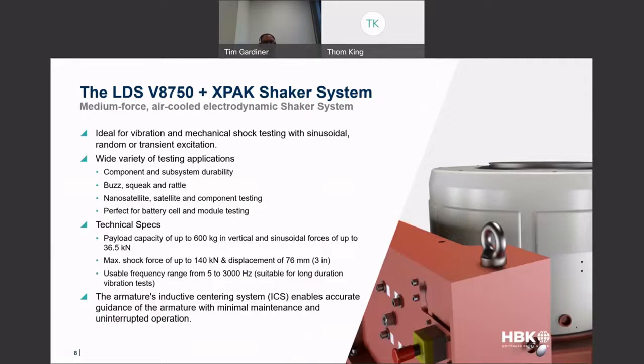So the V8750 and XPAK shaker system is a medium force, air-cooled electrodynamic shaker system. This new system is ideal for vibration and mechanical shock testing, sinusoidal, random, and transient excitation. It can be used for a huge variety of testing applications, all the way from component and subsystem durability, buzz, squeak, and rattle testing, nanosatellite and satellite and component testing, but it's the absolutely perfect system for testing battery cells and module testing. In terms of performance, it has a payload capacity of up to 600 kilograms in vertical, with sinusoidal forces of up to 36.5 kilonewtons. We have a maximum force up to 140 kilonewtons and a displacement of 76 millimeters, or 3 inches.